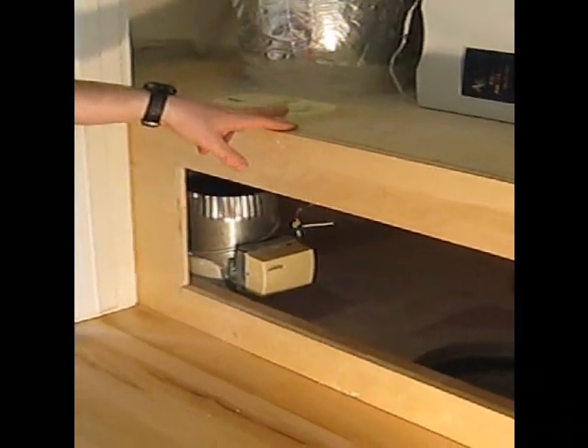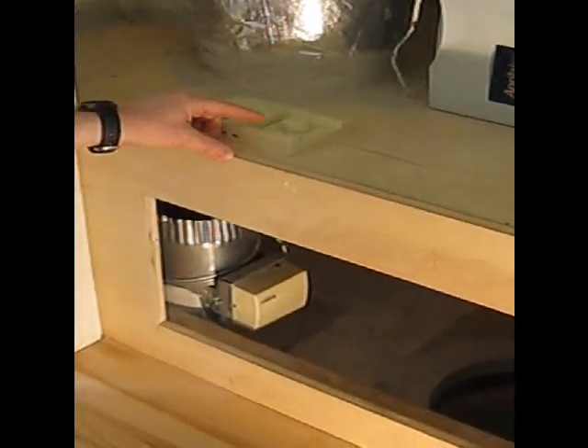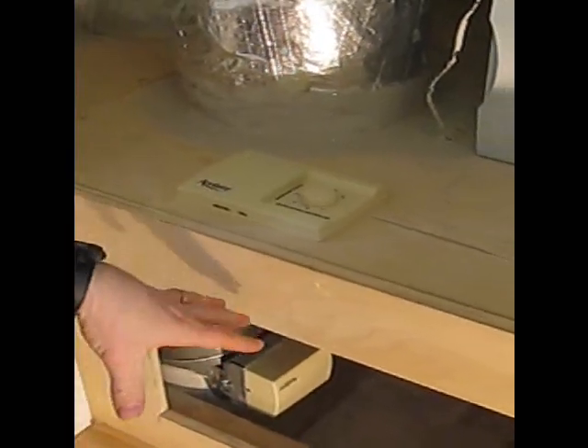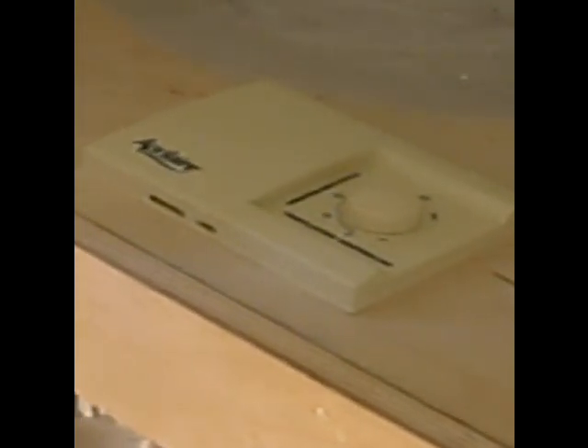And this is the smart controller that's attached to it. This is an Aprilaire system that has a set point where you can set it for a certain number of minutes per hour — in this case we like to set it for 15 minutes every hour — and it's going to open that damper, bring the fresh air in, filter it through your media cleaner, and then send it out through the furnace system by turning the furnace fan on. It's a great system for bringing fresh air into these homes.